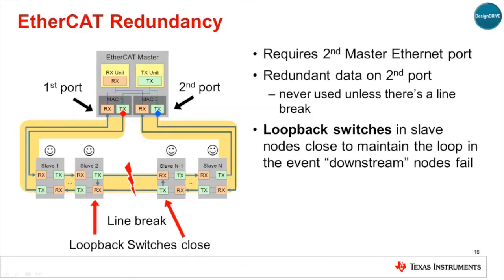By adding a second Ethernet port on the master, EtherCAT can provide cable redundancy. This example shows redundant data being transmitted on the second Ethernet port — an exact copy of that being transmitted on the first master port — but the second port's data is never used by the slaves unless a line break is detected. If a line failure does occur, in this case just after slave number 2, then the associated loopback switches, circled here, will close, thereby completing separate loops and allowing the master to detect the failure while maintaining full communications to all nodes.